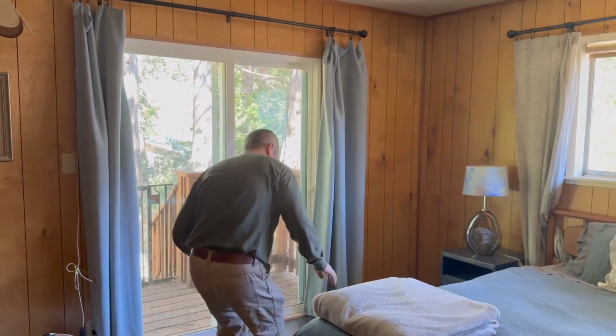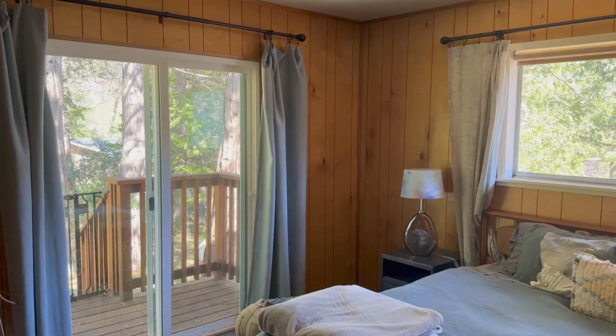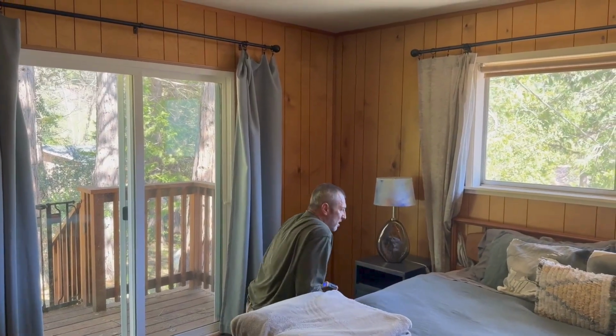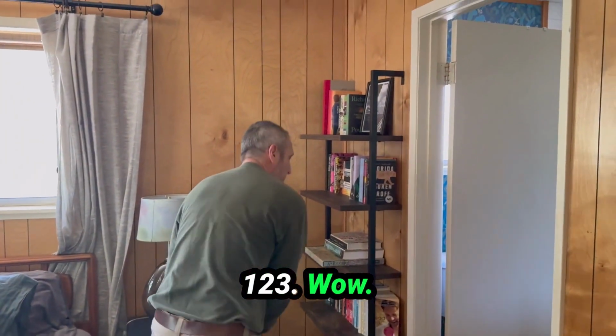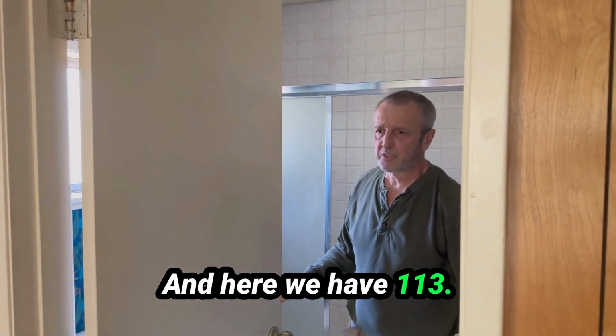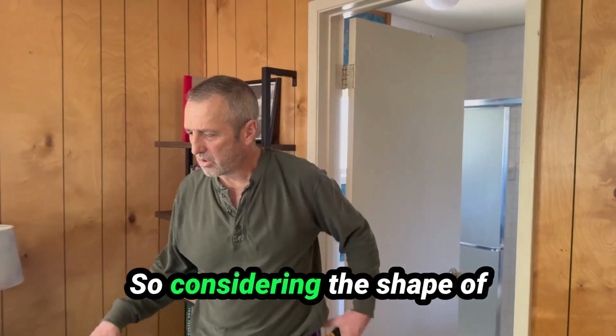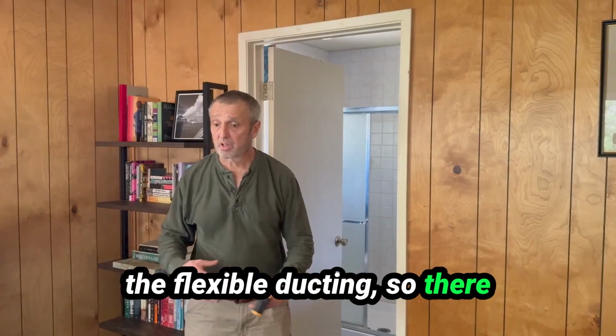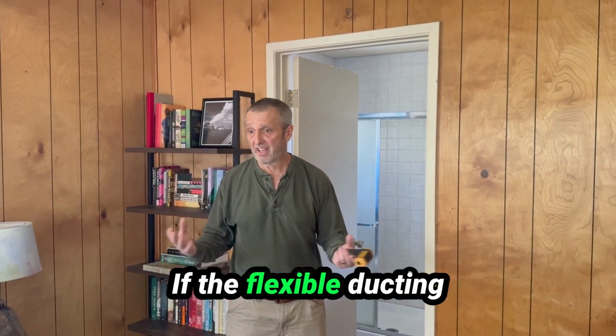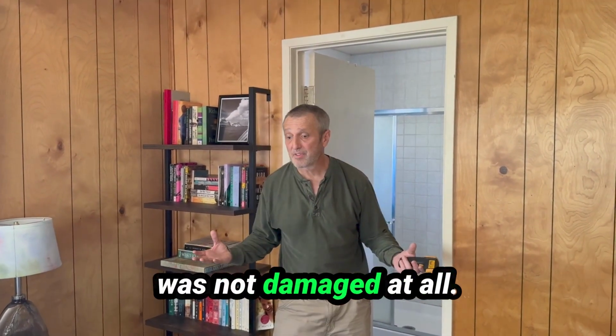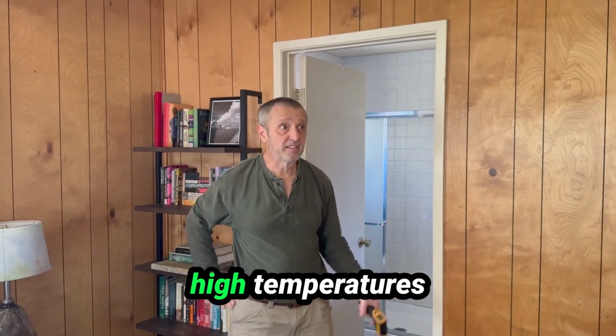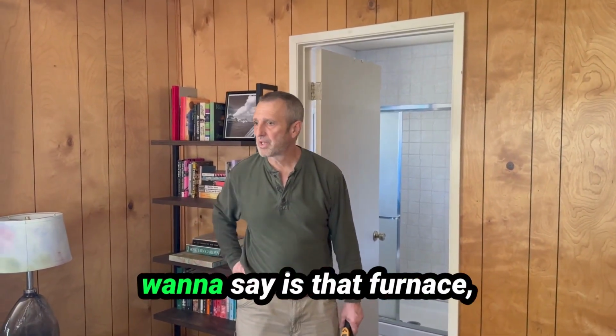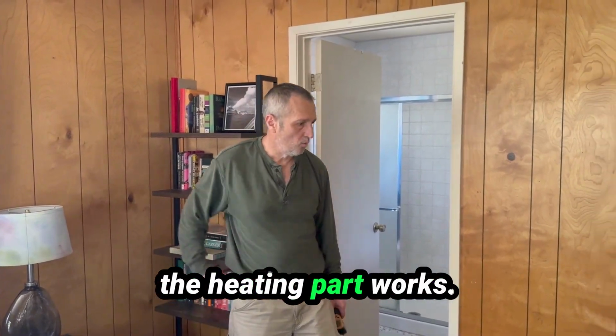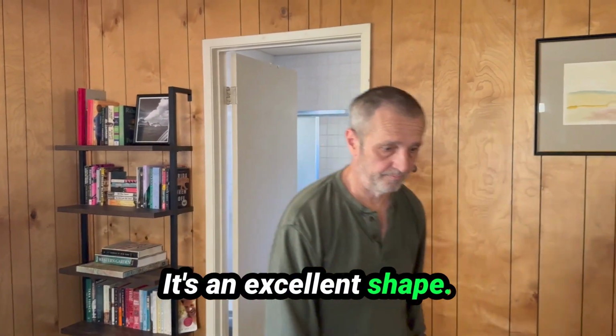112. 123, wow. And here we have 113. Considering the shape of the flexible ducting, there are multiple leaks right there. If the flexible ducting was not damaged at all, we would have amazingly high temperatures inside the house. So what I'd want to say is that the furnace, the heating part, works. It's in excellent shape.